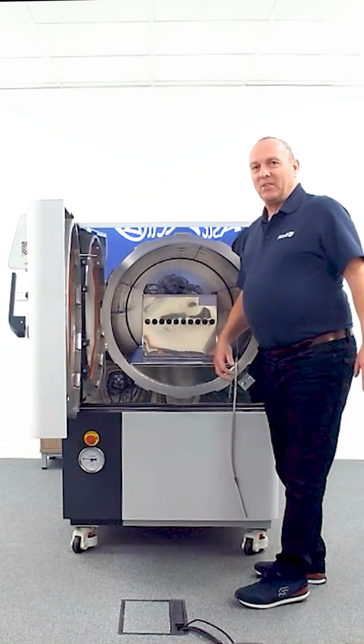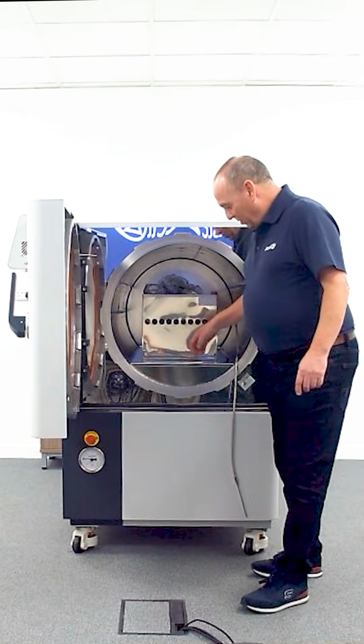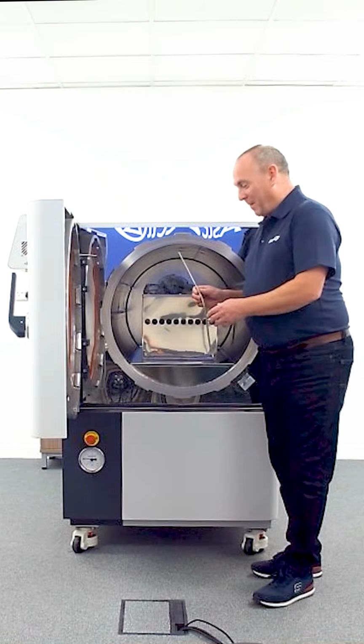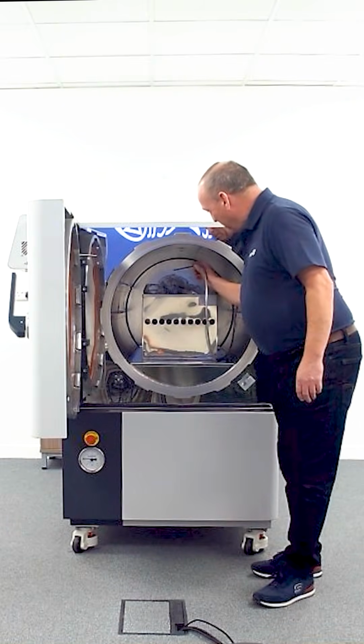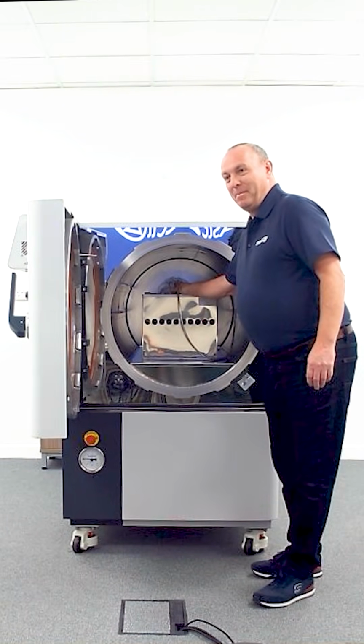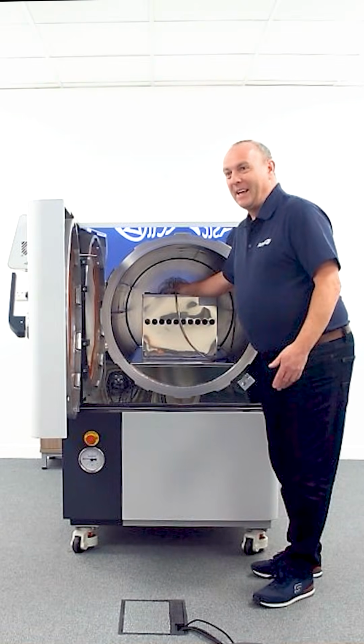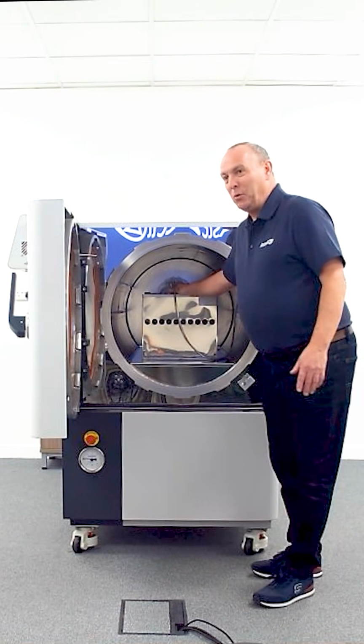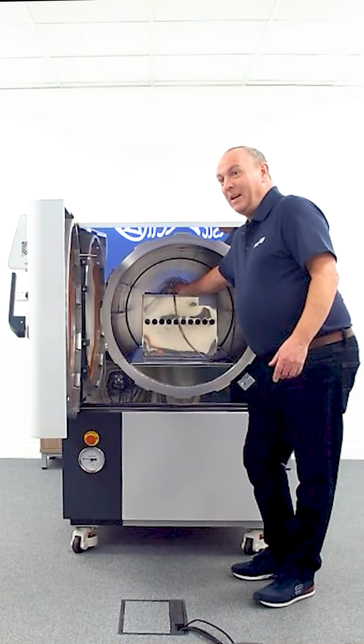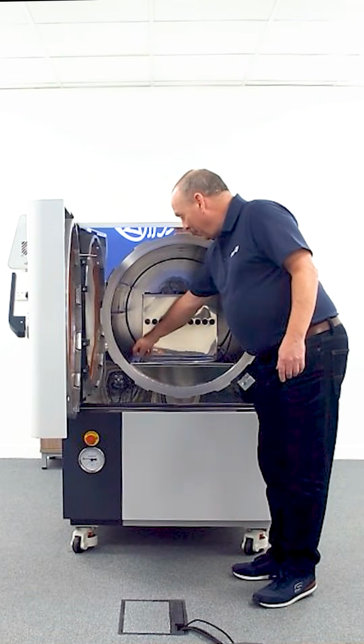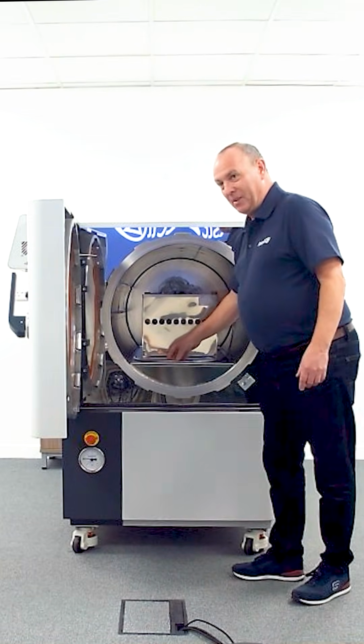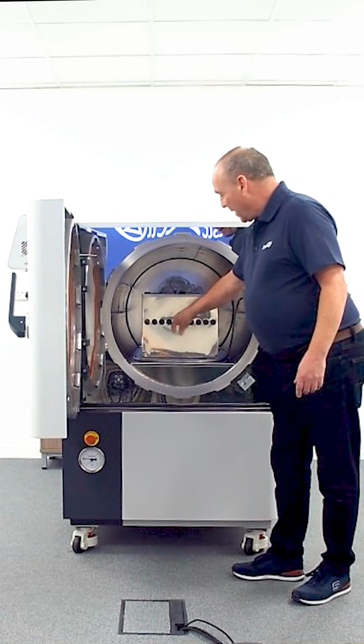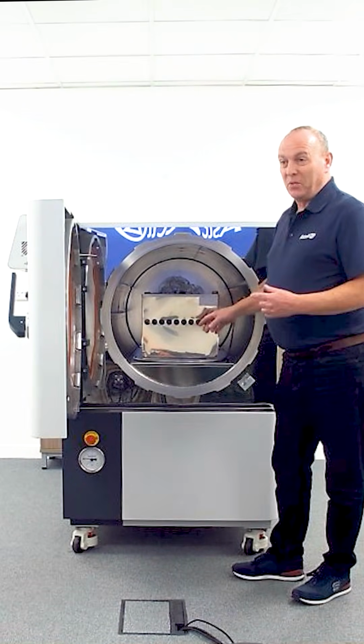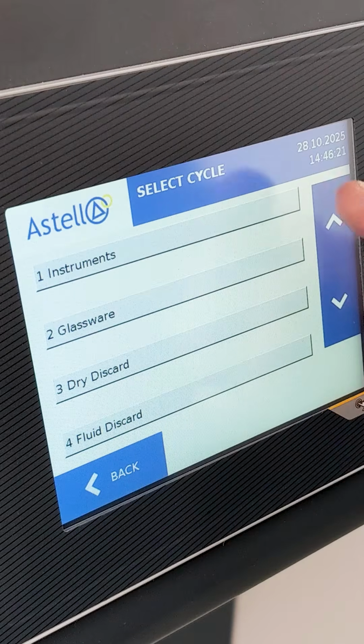The difference with a discard load to a media load is that it does not use the load probe. So we do not put the load probe in the bag, because otherwise it will melt to the plastic and then it's very difficult to get out and you'll probably damage the probe in doing so. So the probe normally gets left tucked down the side of the Morrison container, because the probe is also not turned on in the controller for this particular cycle.